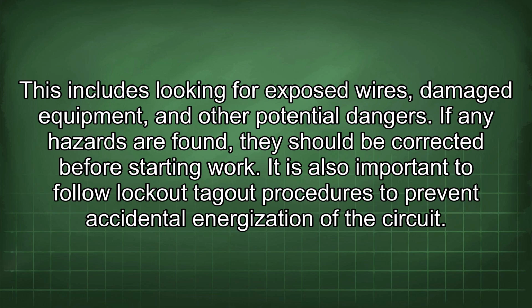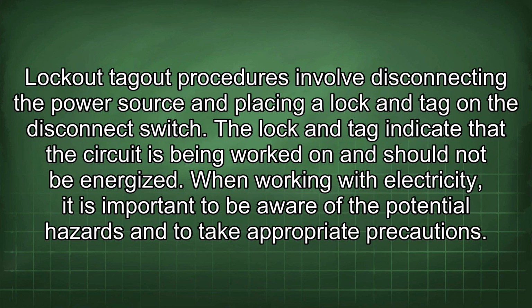It is also important to follow lockout-tagout procedures to prevent accidental energization of the circuit. Lockout-tagout procedures involve disconnecting the power source and placing a lock and tag on the disconnect switch. The lock and tag indicate that the circuit is being worked on and should not be energized.